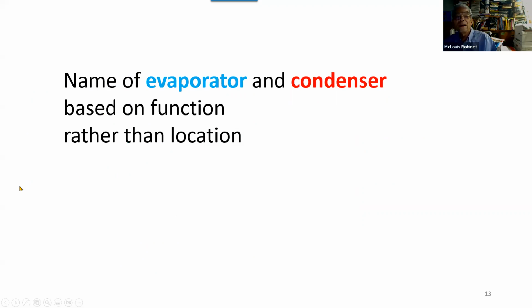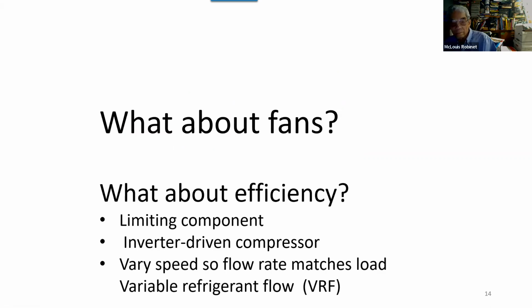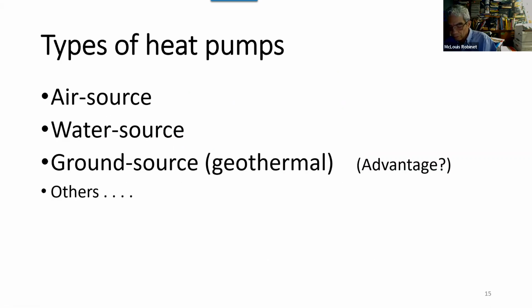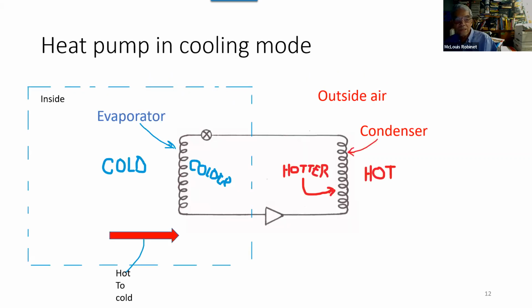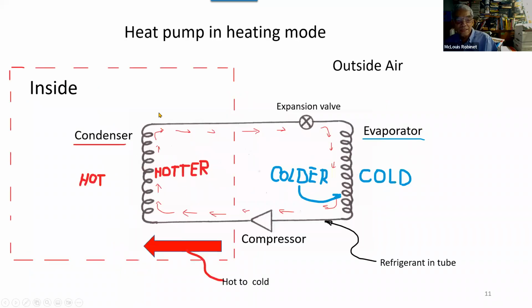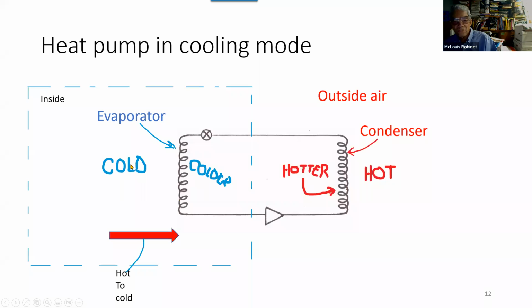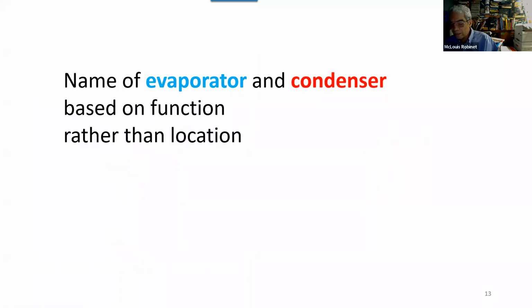Okay, so an important point is the name of the evaporator and the condenser is based on the function, not the location. So let's back up a bit. I want to go the other way. Here you notice that we're calling this the evaporator. Here we're calling it the condenser because we're in the heating mode. So it's the same physical device, its function based on the direction.